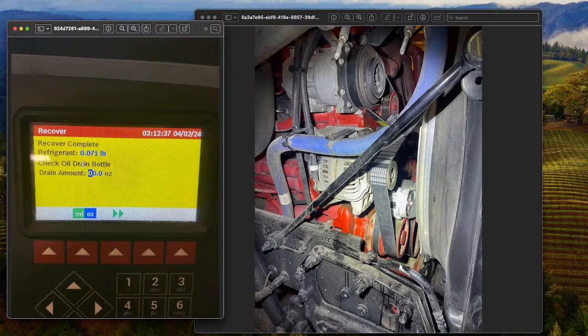For example, this particular system should have anywhere close to around 3 pounds of refrigerant. And as you can see, when it was recovered, there is only 0.071, which is showing low. We would definitely have to refill this. If something has been out of service for a long time, I would caution against just adding Freon. I know I just mentioned in some cases AC systems will need Freon, but AC systems aren't designed to leak out Freon often. You shouldn't have to put Freon in every year.